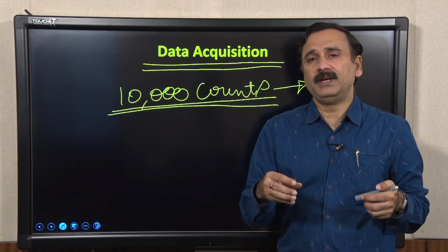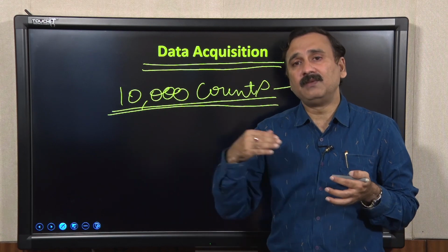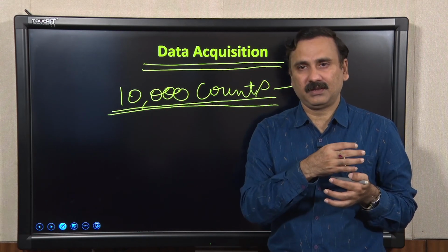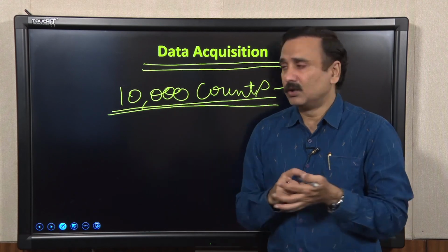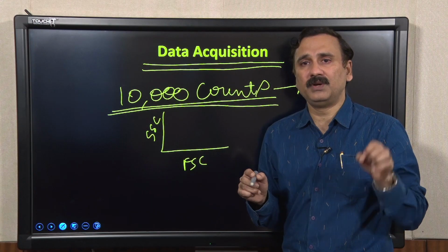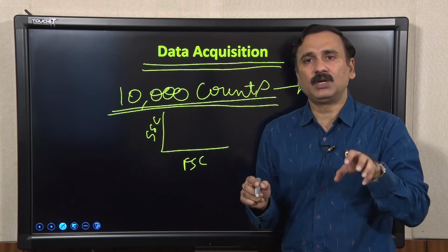When you put the sample into the flow cell, or connect the sample to the machine, it first allows you to draw the sample. So, first you draw the sample without going through the acquisition process. It gives you the option to suck the sample without recording it. Initially, you first see whether the sample is good enough or not, and you do that with the help of SSC versus FSC. So, the first thing you have to do is check the quality of the sample.